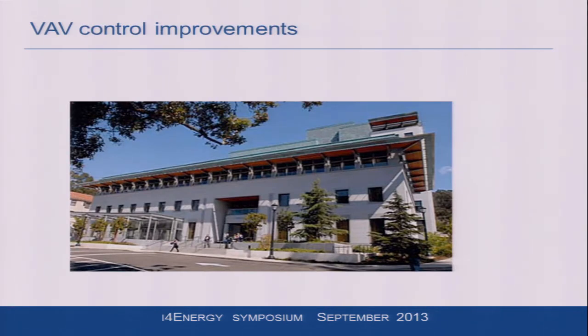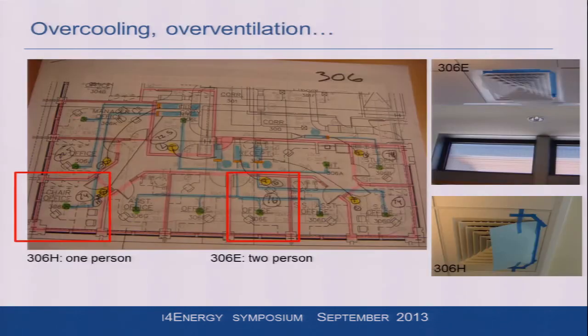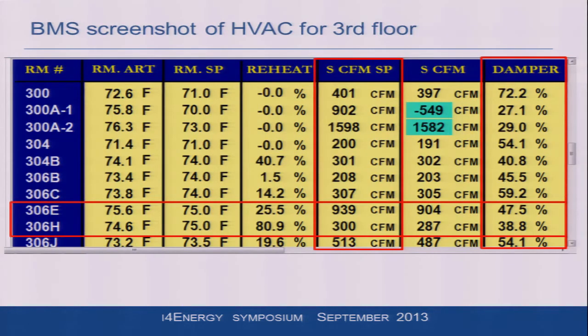This is one of our new buildings. This is our champion for energy consumption on campus, Stanley Hall. It uses somewhere, I understand, close to 20% of campus energy. Here's a couple of rooms in this building. Over here is a room with one occupant. There's 306H, and then there's 306E with two people. Over here you can see diffusers in the ceiling, and they have plastic taped over this one and some fake cardboard on that one.